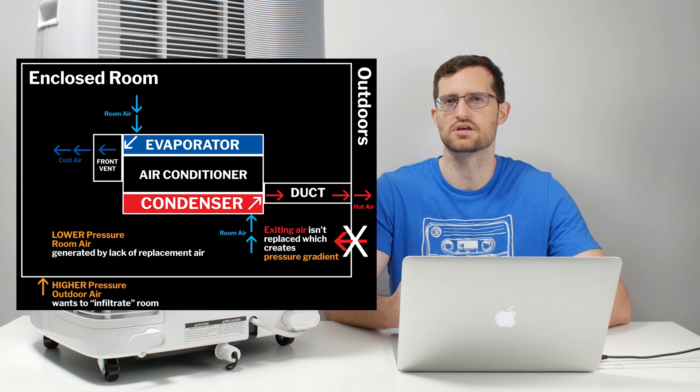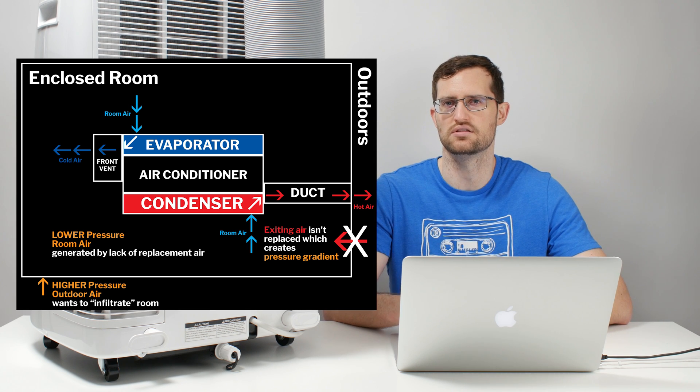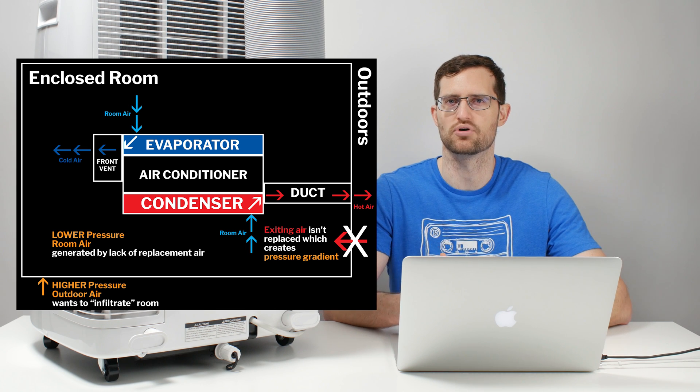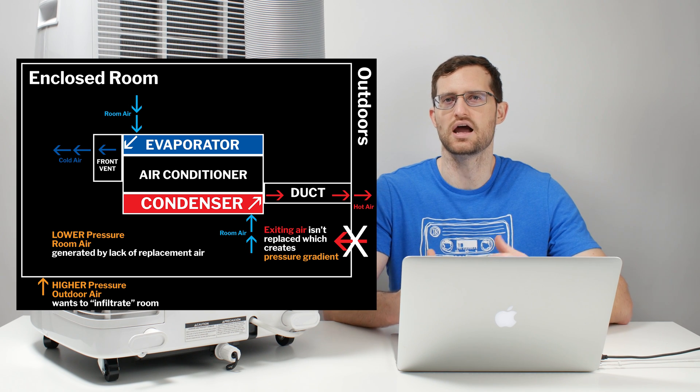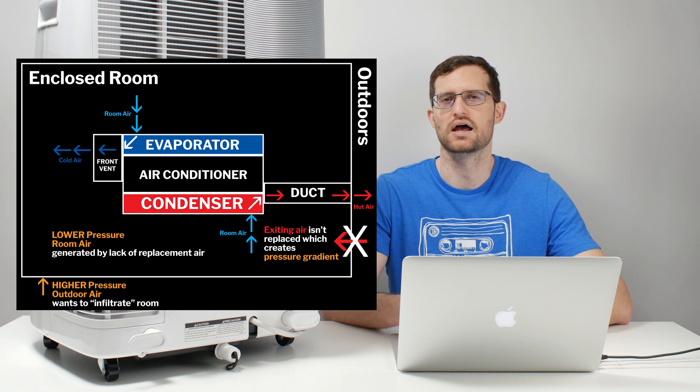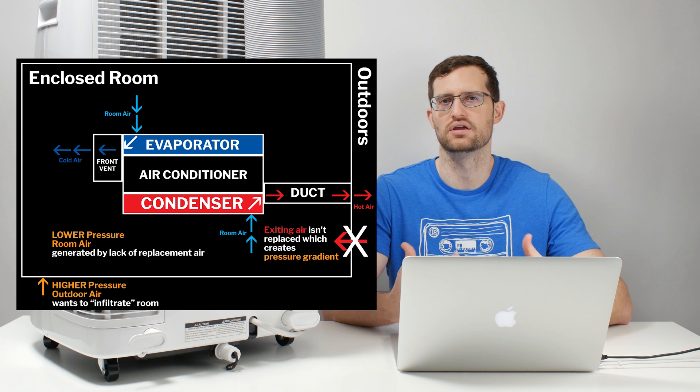So what ends up happening is you create an area of low pressure inside of the room. And by comparison, the outdoor air is at a much higher pressure. So what ends up happening is that the hot outdoor air is constantly wanting to get pulled into the room due to that pressure gradient that's created. And that hot outdoor air is called infiltration air.